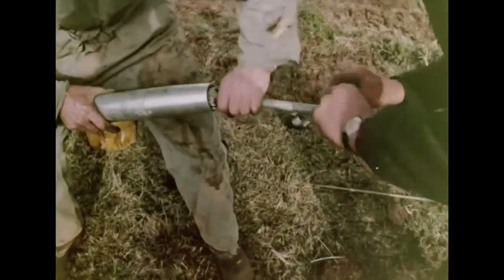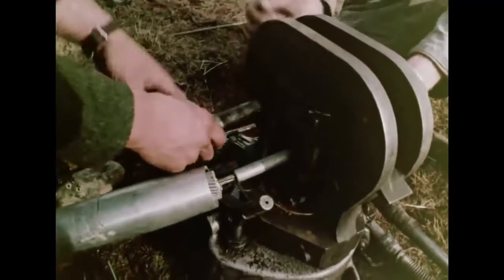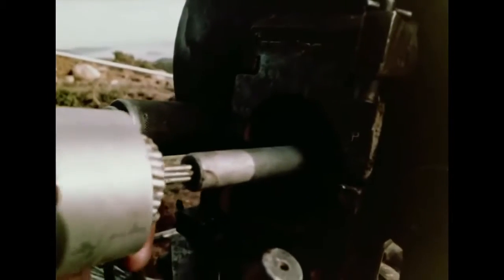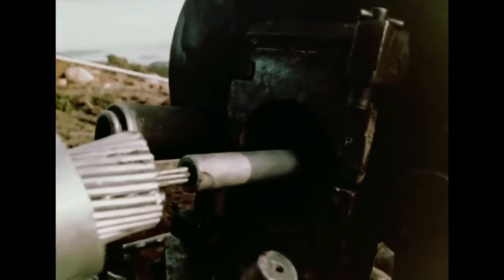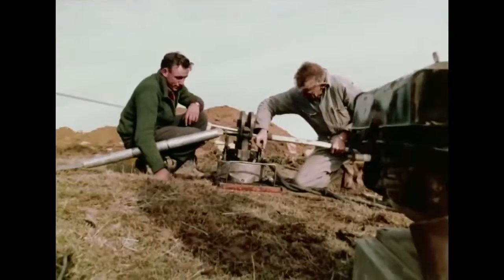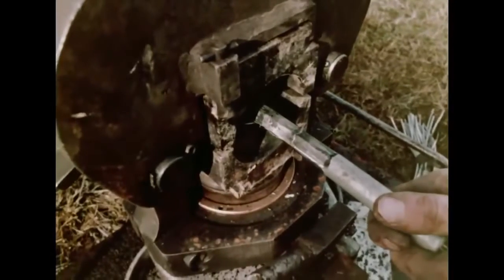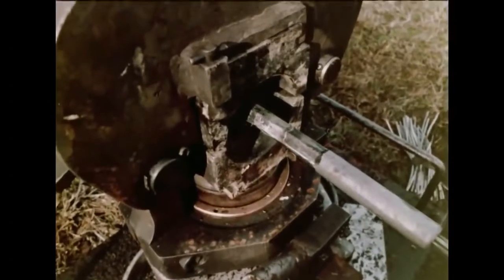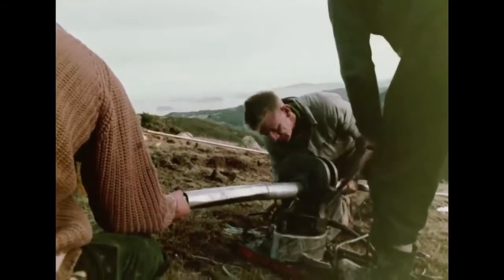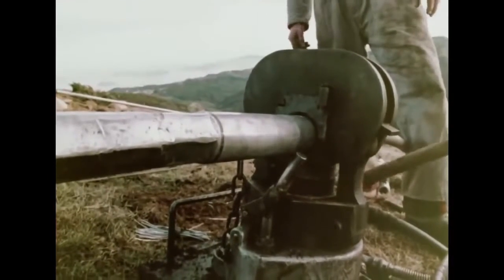A steel inner sleeve joins the steel cores together with the aid of a 100-ton compressor. Both motorized and hand compressors are in use. Outside, a conducting sleeve of aluminium completes the joint. This also is closed onto the conductor with a compressor.